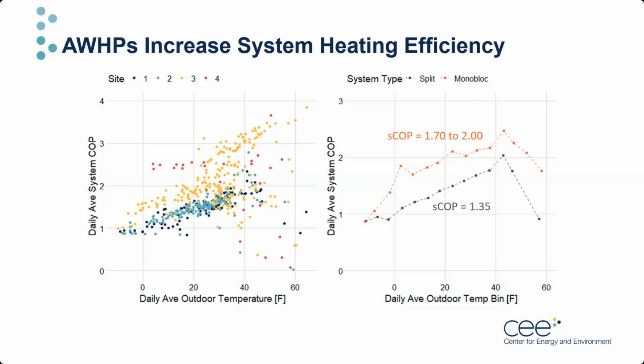The third-party split systems at sites 1 and 2 proved less efficient than either monoblock system below about 30 Fahrenheit, but their average performance exceeded that of the monoblock at site 4 above 30 Fahrenheit. As expected, daily COPs across the board were best in the warmest weather. The reason they dropped so sharply above this point is simply because there was very little heating load at those temperatures, resulting in very low daily COPs due to the effects of standby energy.